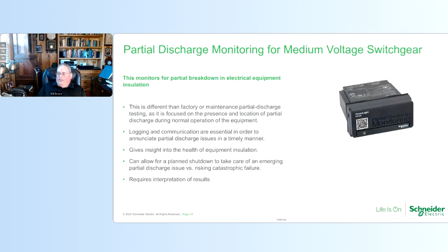For medium voltage switchgear, partial discharge monitoring allows for identification of insulation defects which may develop over time. Unlike factory partial discharge testing, this is not a single test, but a continuous monitoring for partial discharges. So what are partial discharges? Well, partial discharges are so called due to the fact that they consist of arcing discharges in voids in switchgear insulation. But these arcs don't go through the entire thickness of the insulation. If they can be caught early before they develop into full insulation failure, then costly equipment downtime can be avoided. Partial discharge monitoring typically operates through electromagnetic or acoustic sensing. The results require interpretation, though, much like a radiologist interprets an X-ray. Without interpretation, the data wouldn't mean much.